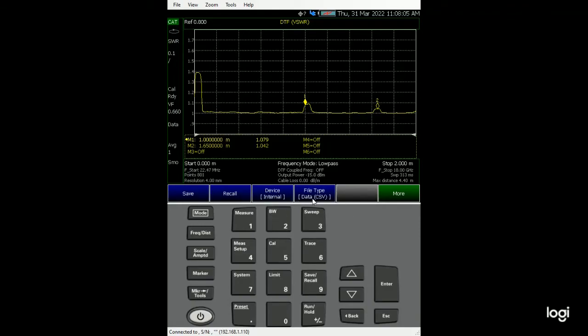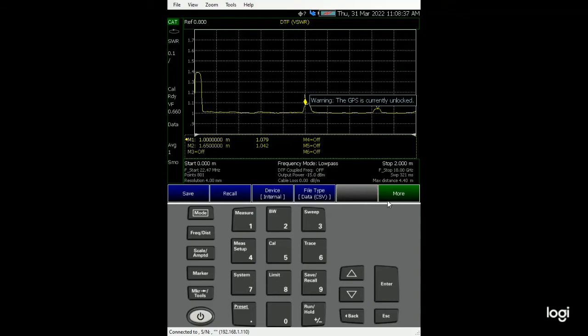What we can do is go back to Escape, Save and Recall, File Type, make sure it's CSV, and then we save it as this. We can name it Cable Under Test, Cable 01, then we put DTF VSWR.